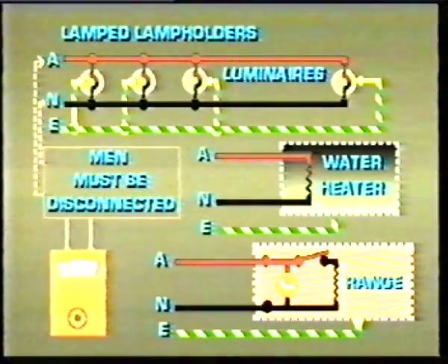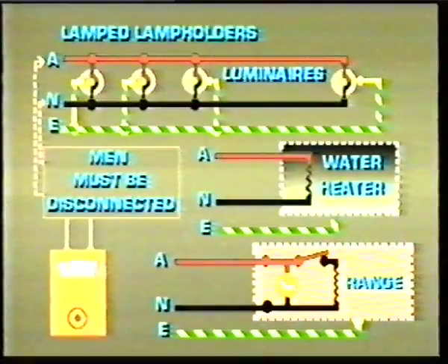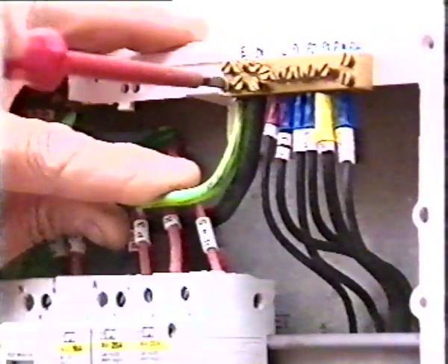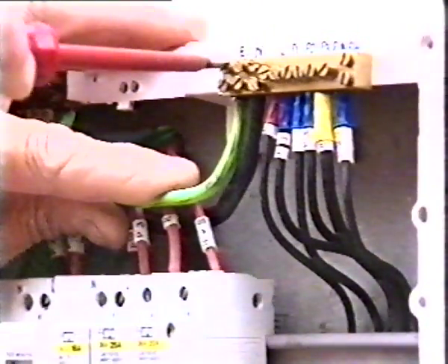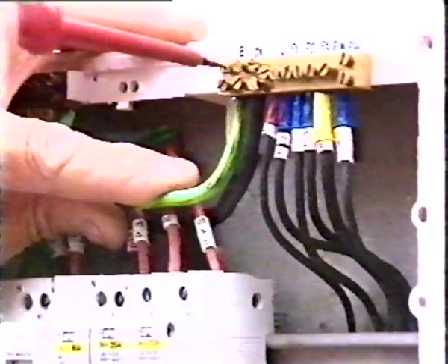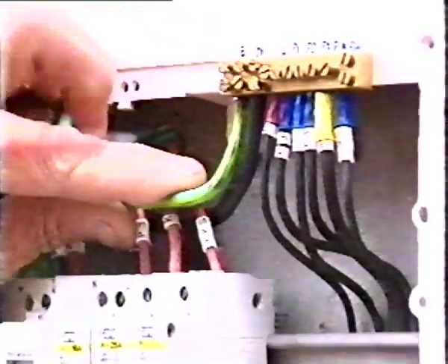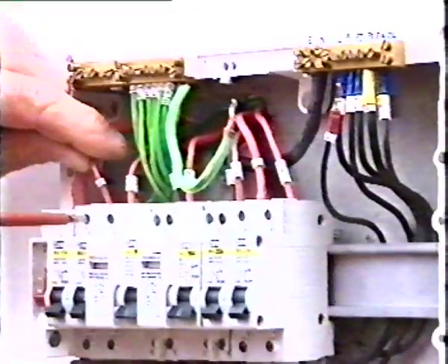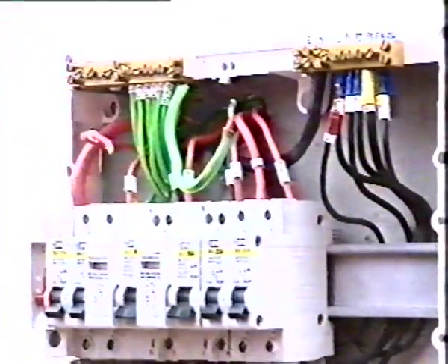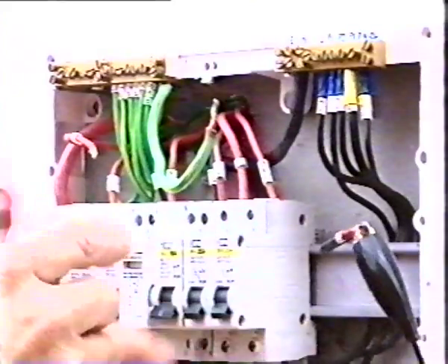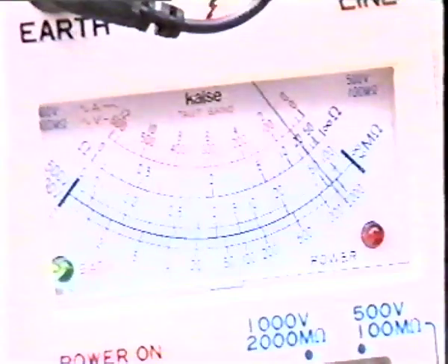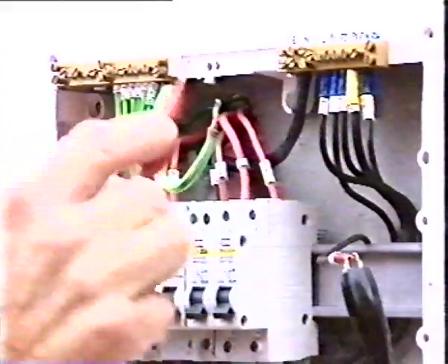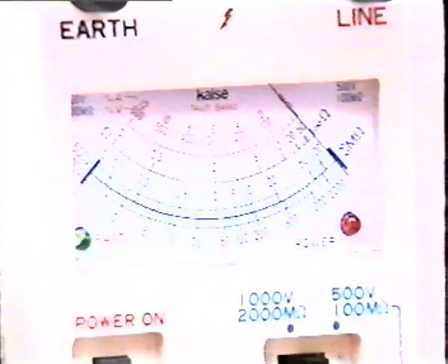First of all, let's test appliances and luminaires connected to fixed wiring. For this test, the MEN connection should be disconnected and all switches in these circuits must be closed. The ohm meter is then connected in turn between the active and neutral, active and earth, and neutral and earth for each circuit. Correct connection is proved by the ohm meter indicating circuit load resistance between active and neutral, and an open circuit between active and earth and neutral and earth.